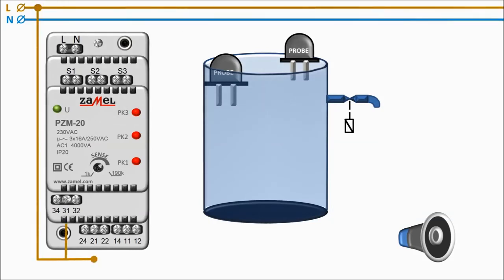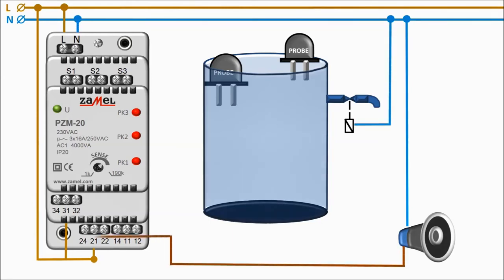The diagram shows the automatic liquid level control system. When the liquid reaches the probe level S2, it is a bottom probe. The solenoid valve will open, allowing liquid to flow out of the tank. In the case of excessive increase of the liquid level, the alarm triggered by the second flooded probe will be activated. This is the S3 probe.